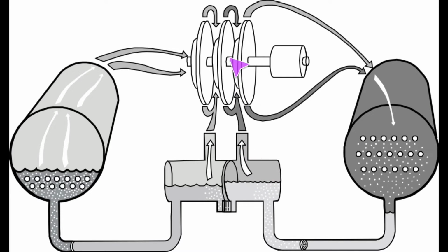So the 20% gets pulled back into the final stage impeller, okay, stage 3, and the 80% gets pushed through a second stage flash plate here inside the economizer. This is all built into the economizer. So we go through this second stage and it all flashes off.